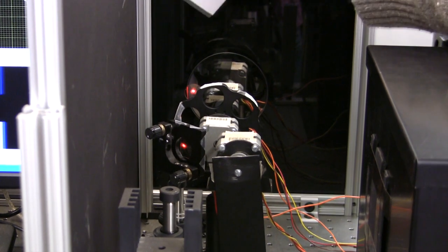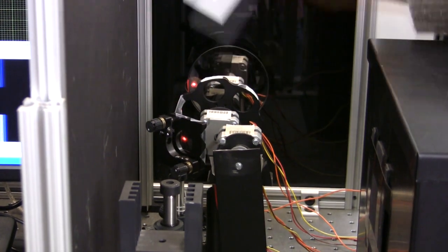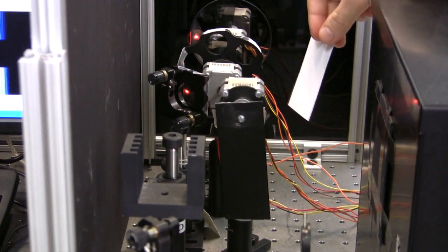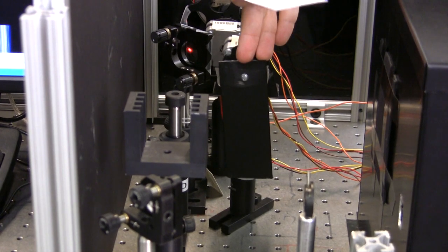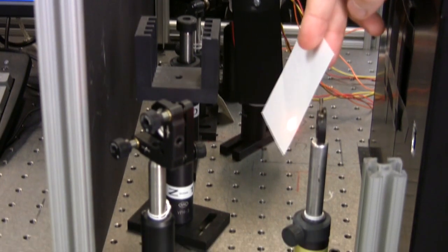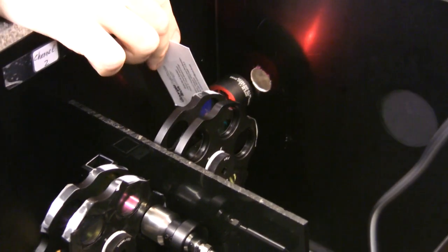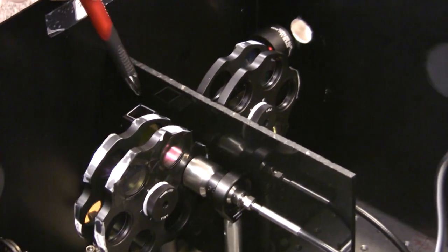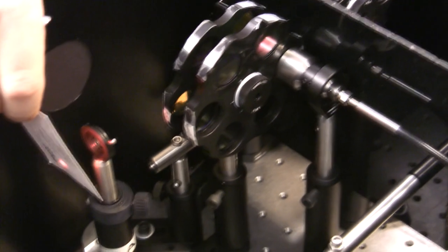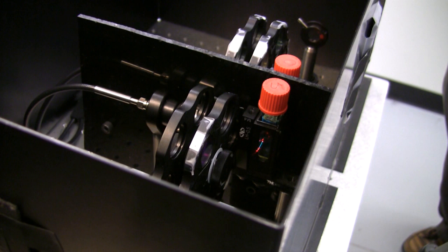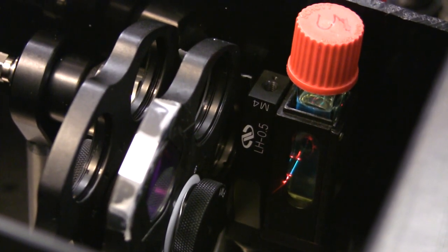The light comes from the mirror behind this wall, then comes from the neutral density filter, comes from a set of neutral density filters mounted in the wheel. Portion of the light gets reflected from the beam sampler and goes into reference channel. The rest of the light goes through the shutter through the filter holder, gets into the mirror and gets reflected into pinhole and then enters into device. After entering the black box the beam goes through the lens and gets focused in the middle of two sample holders. One of them is for sample, for known sample and one of them is for reference. The beam gets then passed through the second pinhole and gets dumped. So you can see fluorescence coming out of the light excited, and fluorescence is green and the excitation is red which means there are two photons being absorbed to excite this fluorescence.